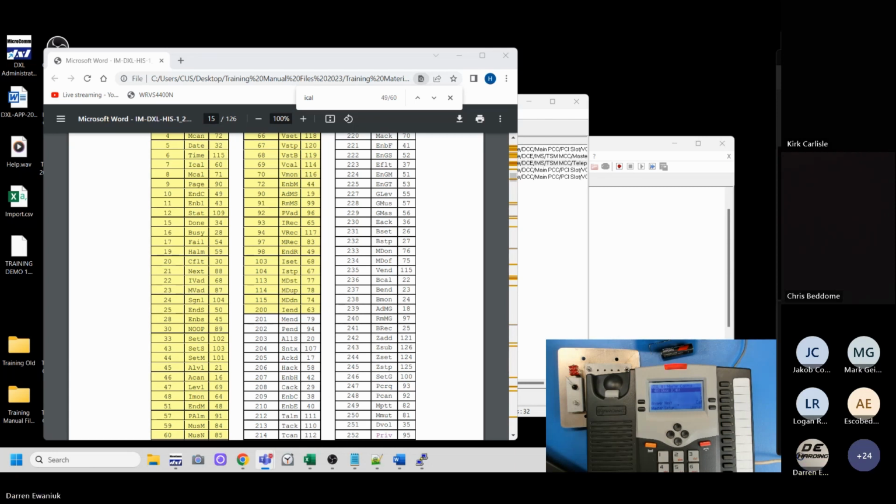The first method, which is the only method available on DXL, works exactly the same as what I just discussed on this text interface. So the first method is a message-based system. So instead of sending a text command with up to 4 arguments, you have a block of 5 registers with the command in the first register and the parameters in the following 4 registers.